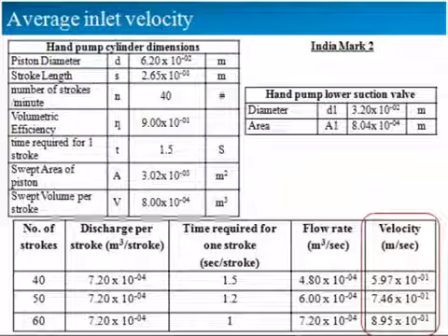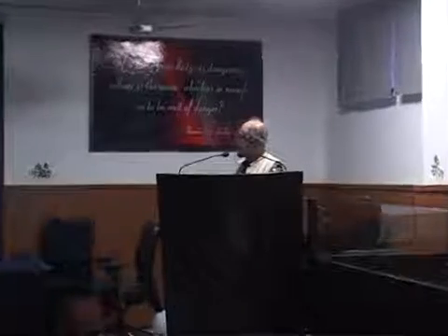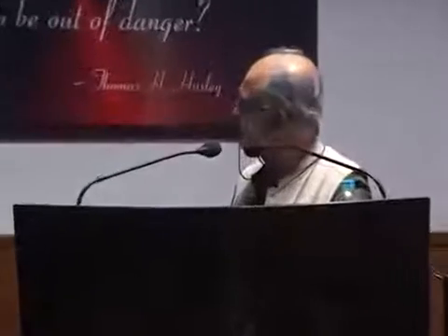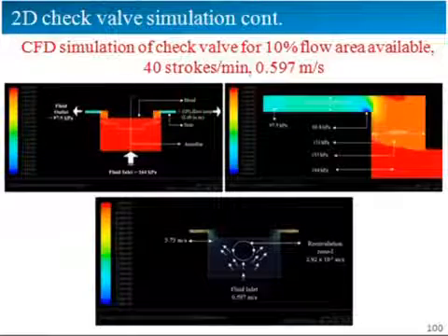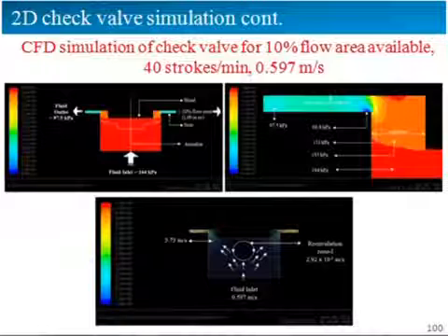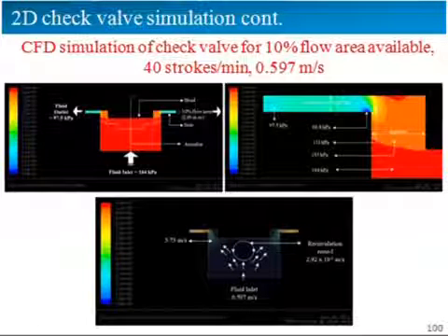You see the velocities which are getting developed. You can manipulate and calculate the changes in the velocity. I can calculate the cavitation number. This will tell me. This is again now done by doing a complete CFD analysis of this particular valve.